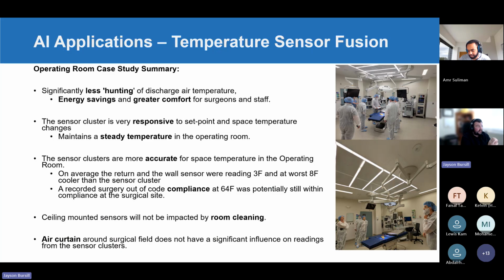But really what happened here, you can see some of these ceiling-mounted sensors all over the place, and they can be pointed a bit more towards the operating table. You get less hunting because you're not using the discharge air temperature sensor as a reference.